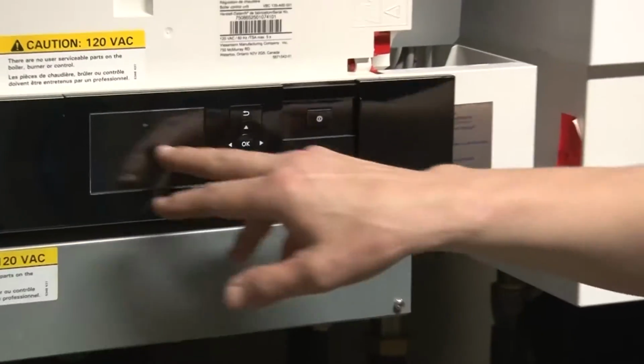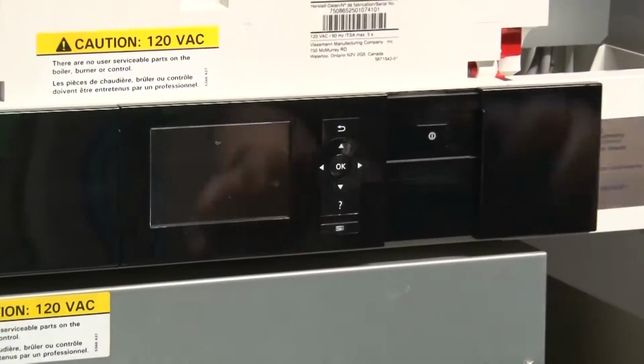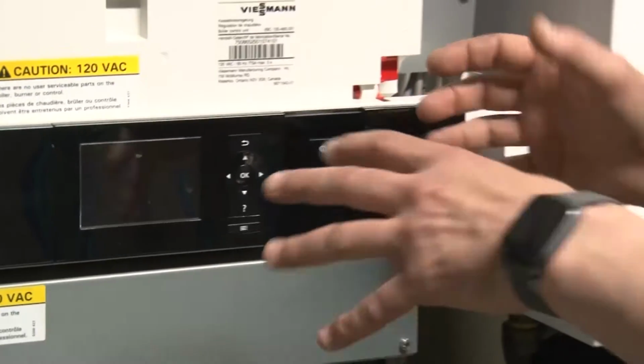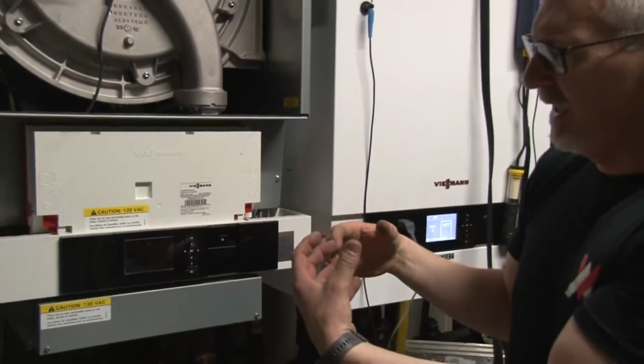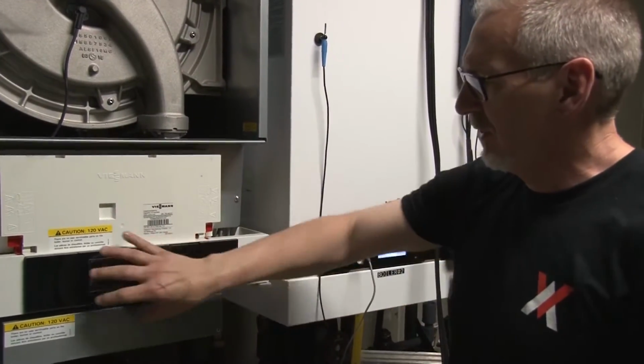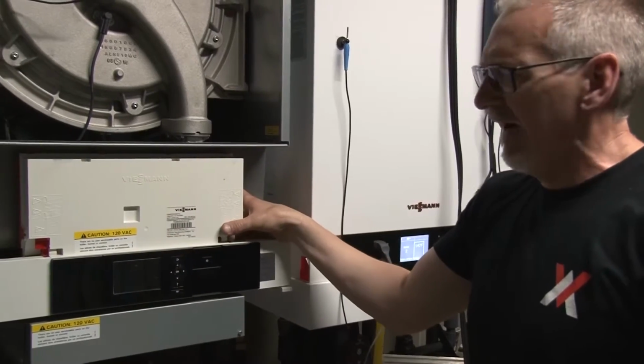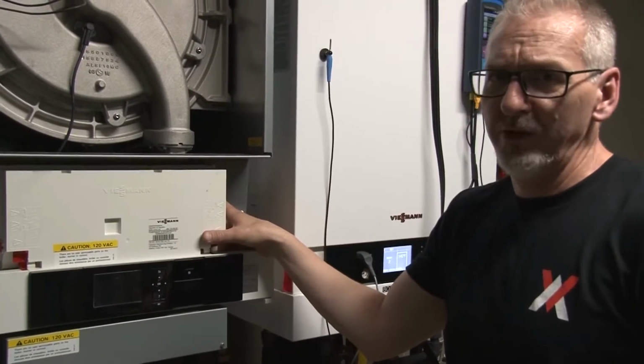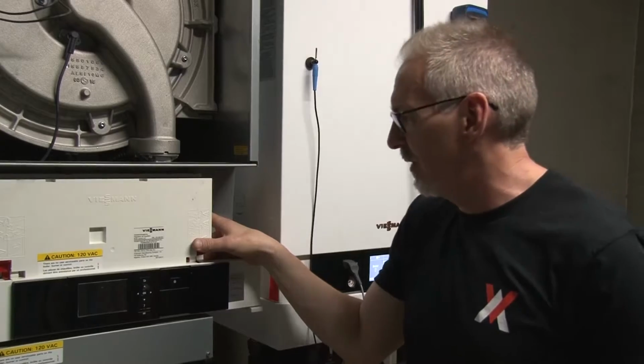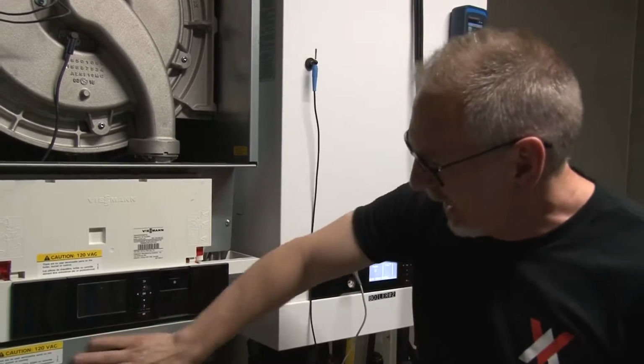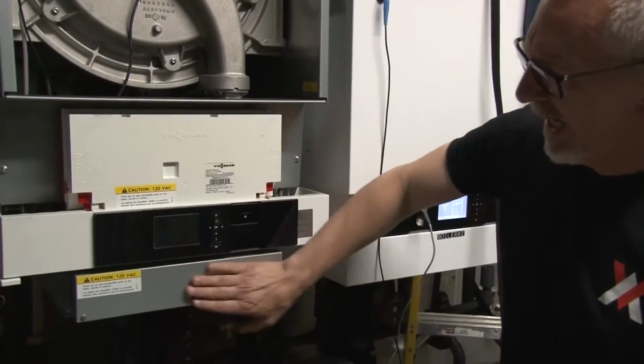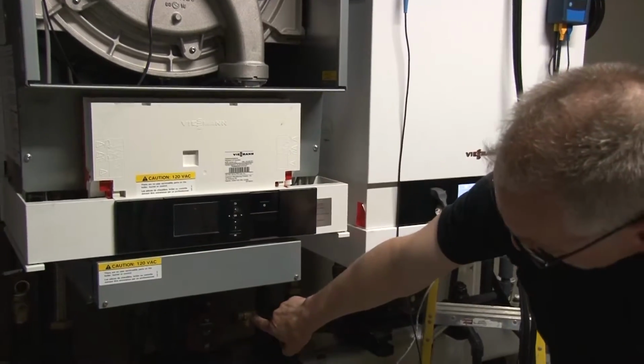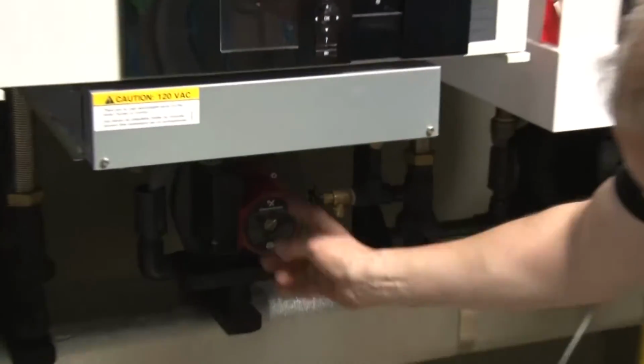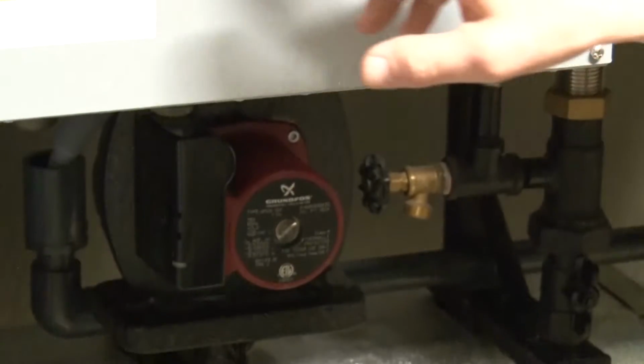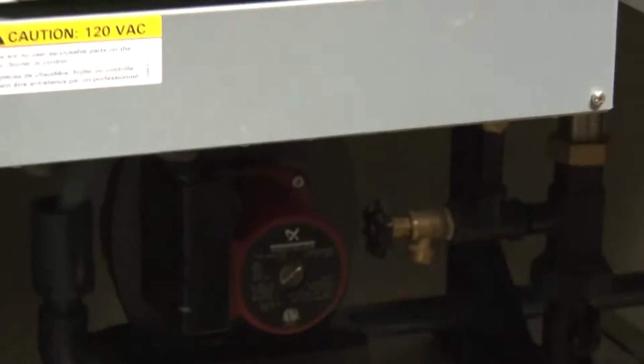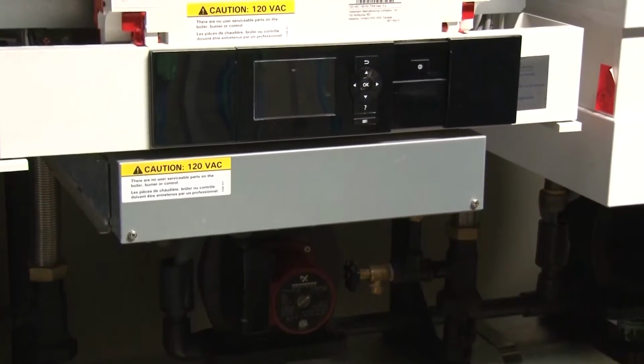Power button, powered off, display goes down, that's blank. There's still power in the control, so if we're pulling this control out and doing troubleshooting, you have to be aware that even though there's no screen here, there's still live power in the back of this control. We're not going to do that today. We're strictly about service, not so much about troubleshooting. In behind here is where you do a lot of your field wiring. Your boiler pump, for instance, on the bottom here, this little fella that's pumping water through the boiler whenever it's firing up, is wired directly to this little junction box on the bottom of the boiler.